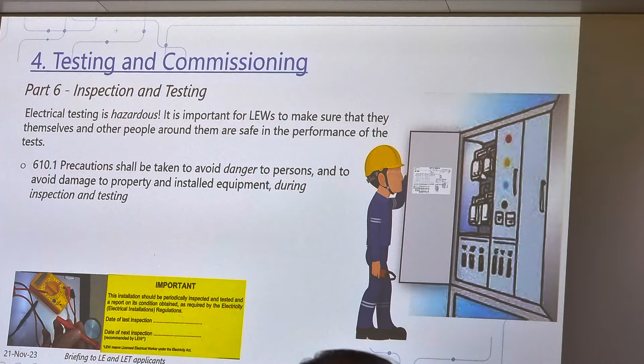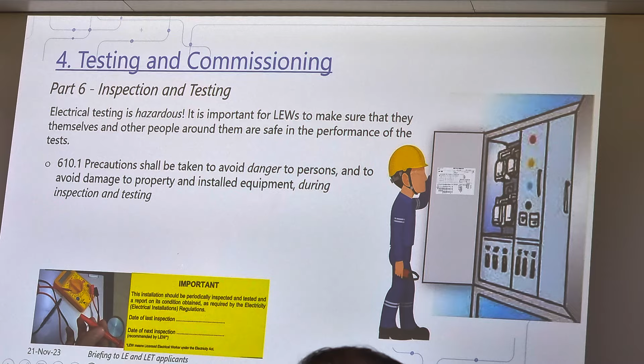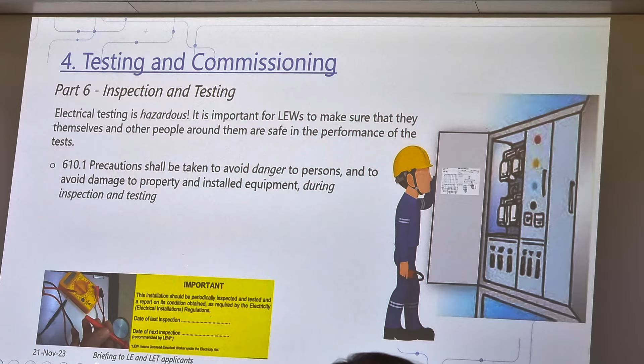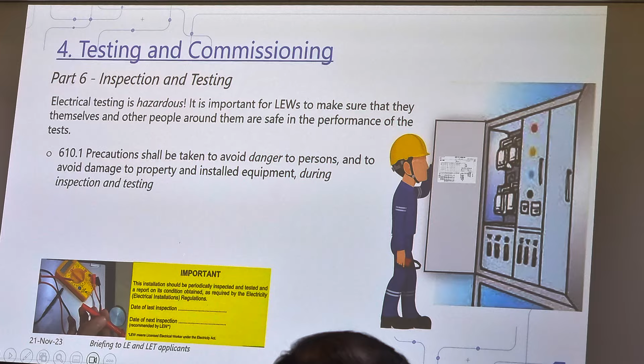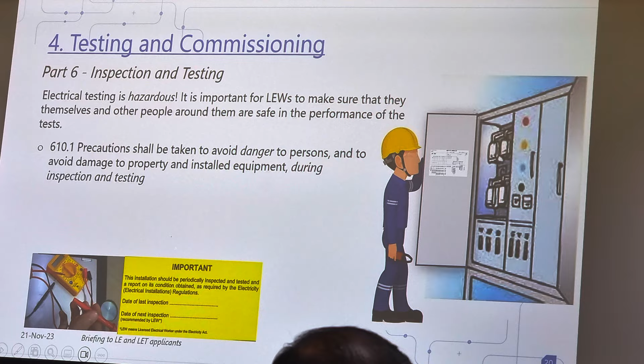So I want to highlight 610.1. Precautions should be taken to avoid danger to the person and to avoid damage to property and installed equipment during inspection and testing. So this is important because when you do a test, it will cause damage to the installation. It will cause injury to people who are not aware because they are not LEW. They are helpless. They do not be aware of the danger. You are aware. Once you are aware, you know the danger of testing. So you need to make sure that people around you are also safe.